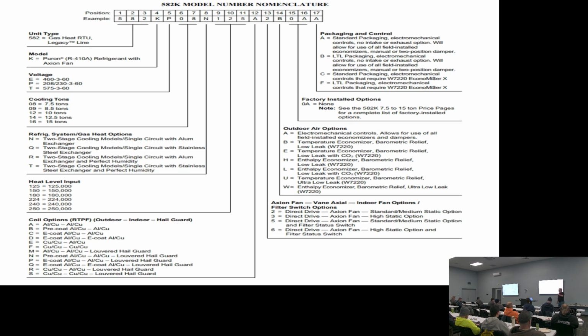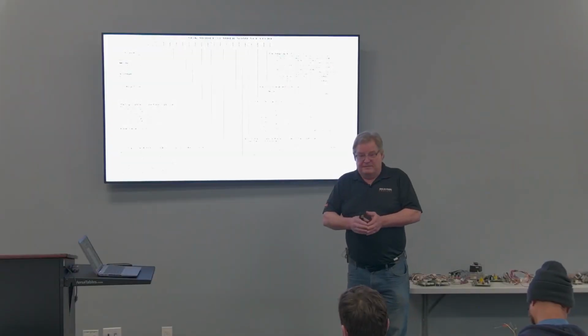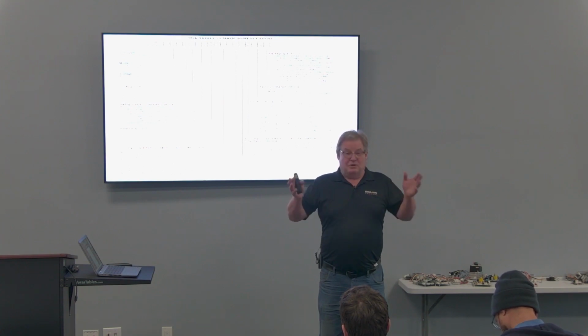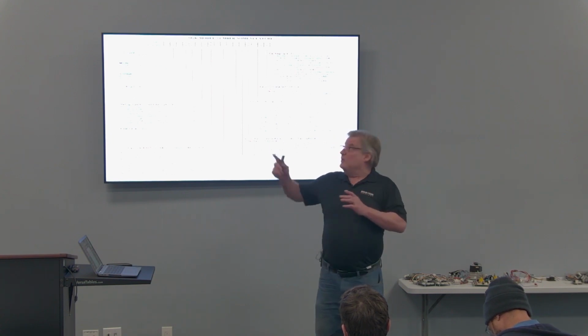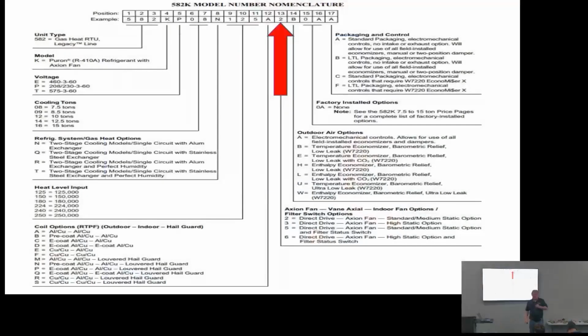Now, our guys are trained to get you the part you need. So if you come in and don't give them all the right information, we're going to try to make some assumptions, right? And blower motors especially. So we have a standard static unit, a medium static unit, and a high static unit. That one right there tells me what blower's in this thing. If you don't get that whole number, and our guys say, well, in this one we normally stock the high static, they're going to give you their own motor. They're going to have to guess. So get that entire number.